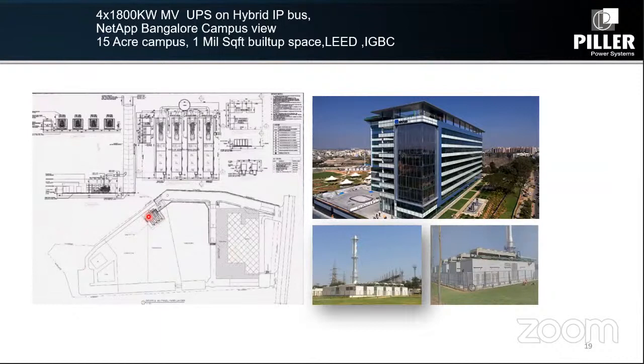This is a hybrid system where the UPS is on 11 kV and the paralleling is done after the step down, and it is in an IP bus configuration, which has its own advantages. You have up to tier 4 certification already available for a constructed facility. We have customers with this configuration at tier 4, but the UPS remains N+1. There is no space consumed inside the building.